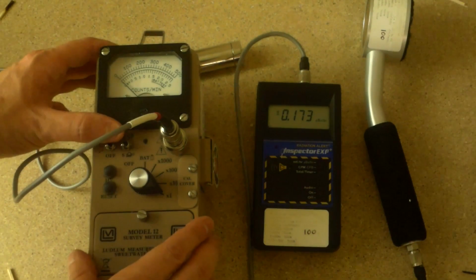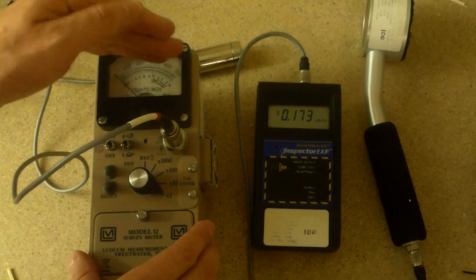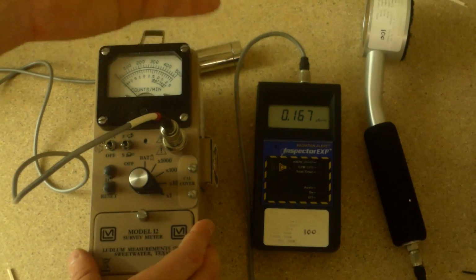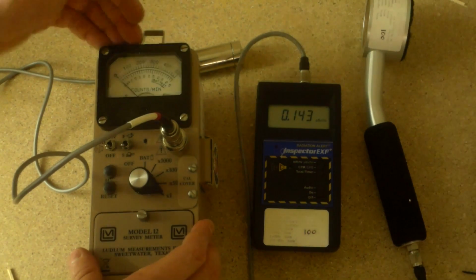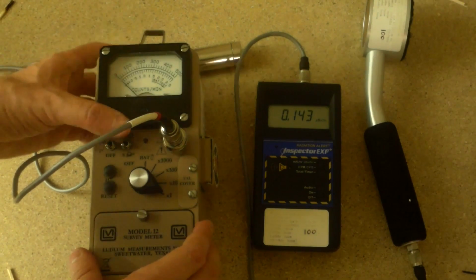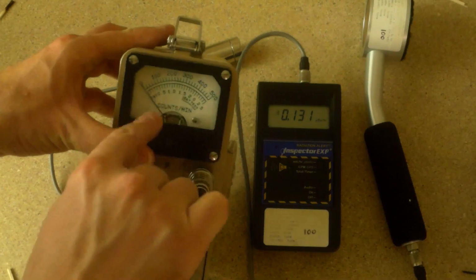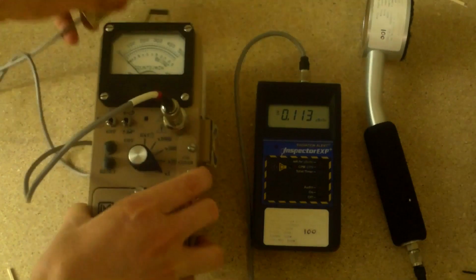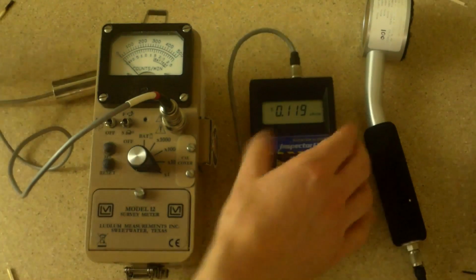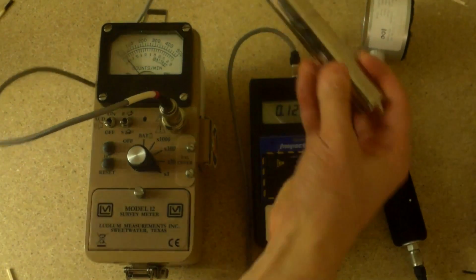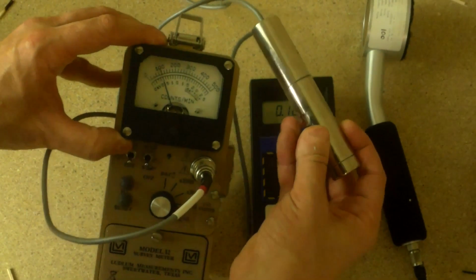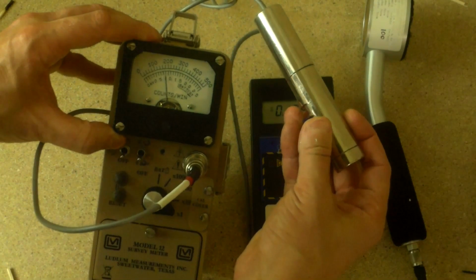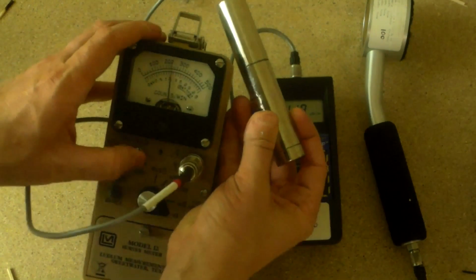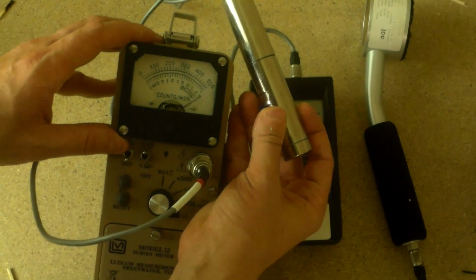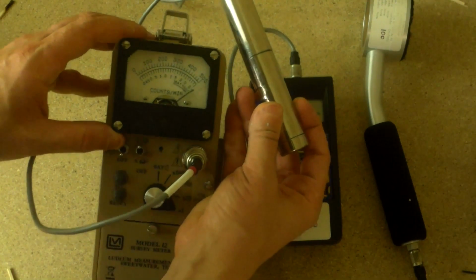The first type of unit is the simple basic count per minute or per second. I guess you could have counts per hour, but I've never seen such a thing. So counts per minute, counts per second. These display on the reading right here. This guy's in counts per minute, for example. When you put it near something radioactive, let's see, where's our little radioactive source? Here we go, cesium-137. So we put it near this, and you see it starts to rise up. See it rising up? And it says that I'm getting 100 counts per minute, 200 counts per minute, and speed it up a little bit there, 400, 500, it's almost off the scale.